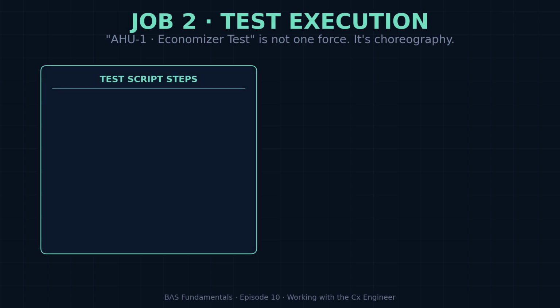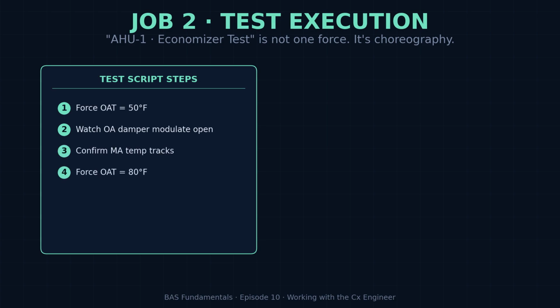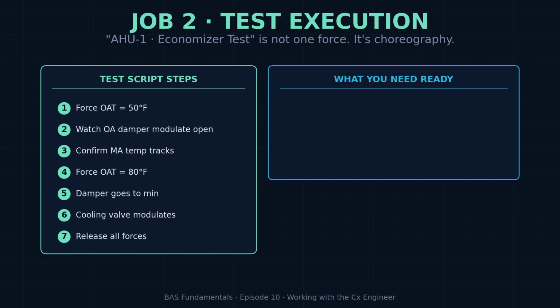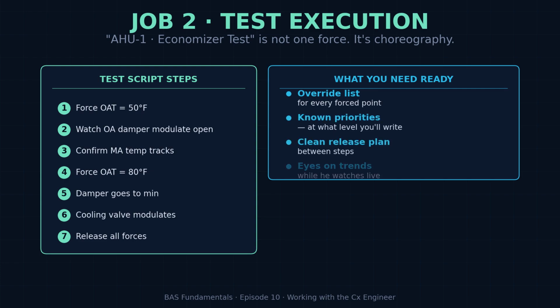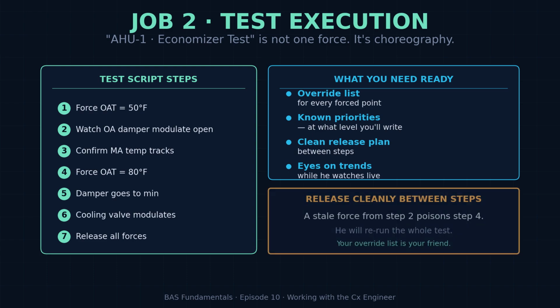Now, test execution. This is the long part. The agent walks up with a single functional test script. Maybe it says AHU1 economizer test. He's going to force the outside air temperature low, watch the mixed air damper, watch the supply temperature, watch the cooling valve, and confirm the sequence behaves exactly as written. That is not one force. That is a whole choreography of forces and releases that you are going to execute while he watches. You need to have your override list ready. You need to know which point gets forced, to what value, for how long before the next step. You need to release cleanly between steps.